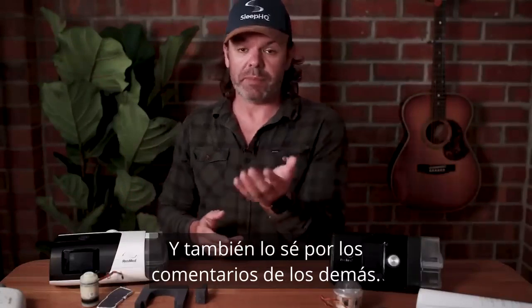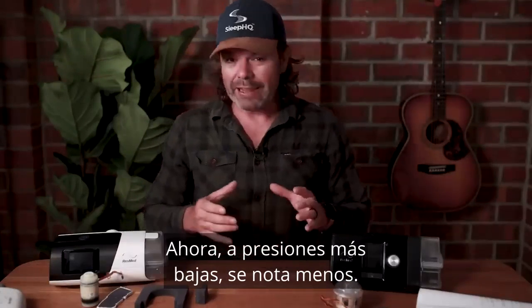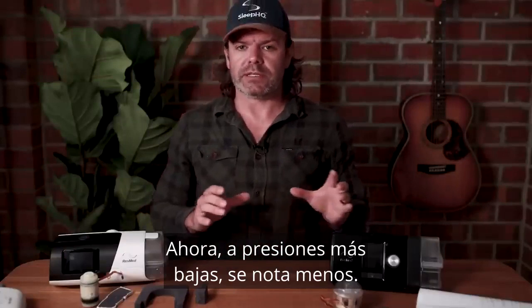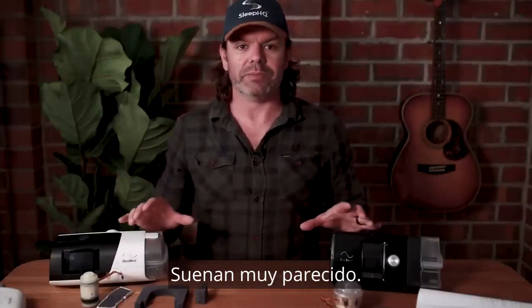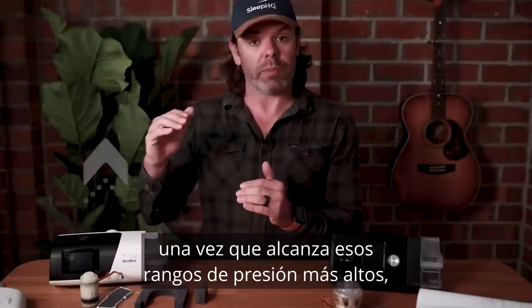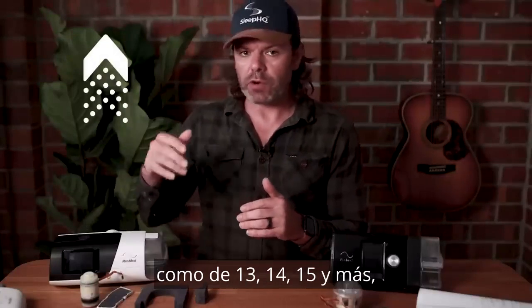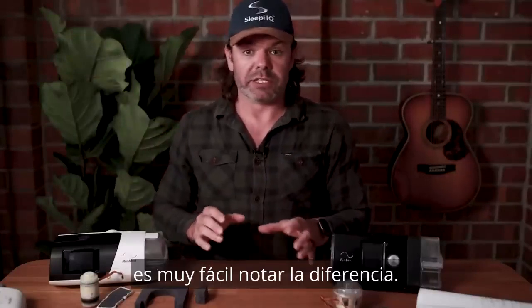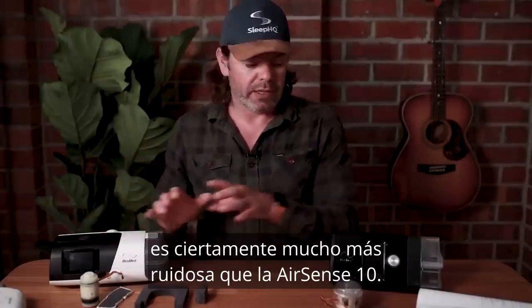And I also know from the feedback from others. Now, at lower pressures it's less noticeable - they sound very similar. However, once you get up into those higher pressure ranges, sort of 13, 14, 15 and above, it's very easy to spot the difference, and the AirSense 11 is certainly a lot noisier than the AirSense 10.